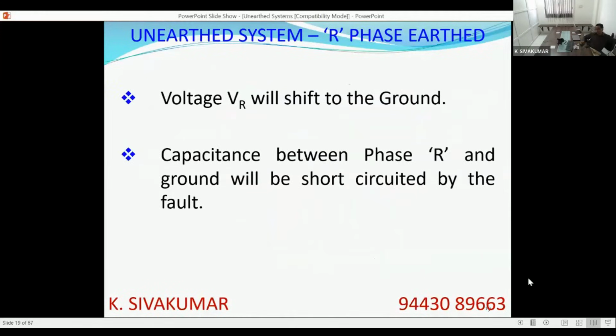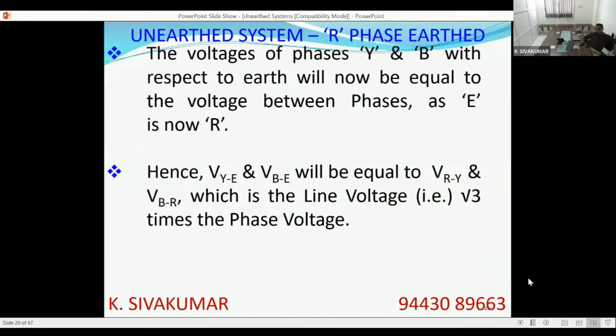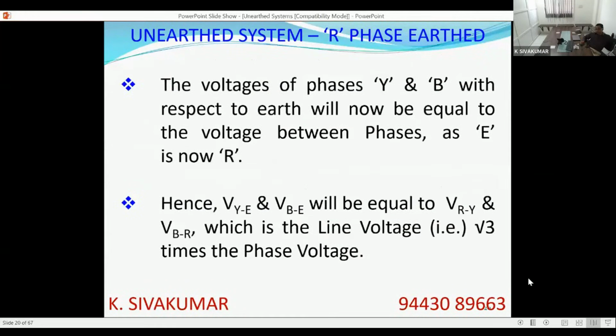Voltage VR will shift to ground. The capacitance between R and ground will be short circuited by the fault. The voltage across Y and B with respect to earth will now be equal to the voltage between phases. As E is no more E, E has become R now. So VYE and VBE will become VRY and VBR, which is the line voltage, that is √3 times the phase voltage.